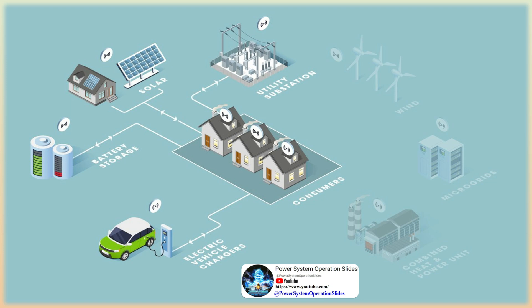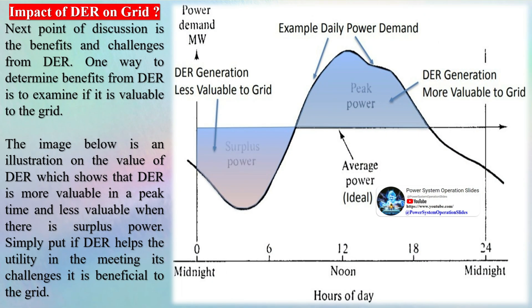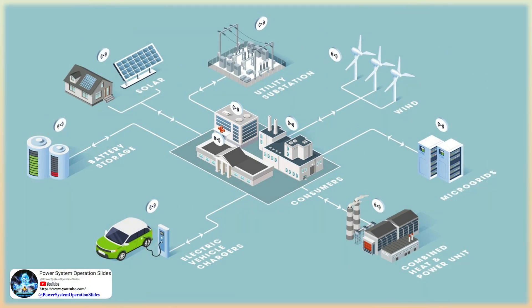The next point of discussion is the benefits and challenges from DER. One way to determine benefits is to examine if DER is valuable to the grid — it is more valuable at peak times and less valuable when there is surplus power. A few benefits from DER include: deferral of distribution network upgrades, reduction in line losses, reduction of emissions, backup power during emergencies, demand charge reduction and energy arbitrage, voltage and frequency support, spinning and non-spinning reserves, and black start support.